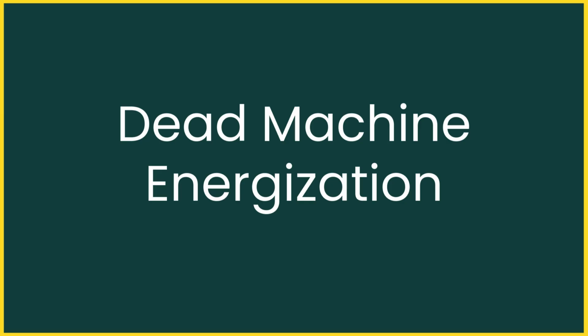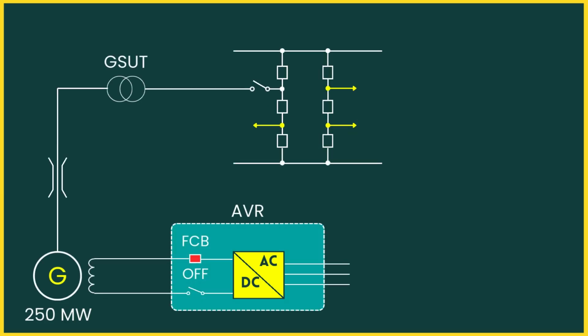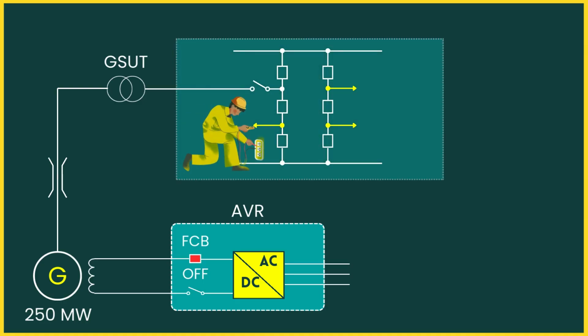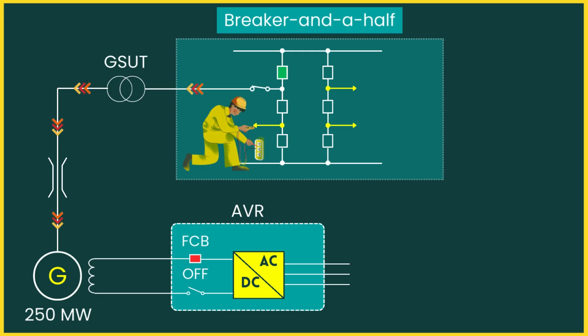To understand how serious this can be, consider one real incident. A 250 megawatt generator in a thermal plant was offline for scheduled maintenance. Its generator protection had been disabled, assuming it was not needed while the machine was offline. A switchyard commissioning engineer, thinking the generator was safely offline, decided to test the control circuit in an adjacent bay of a breaker-and-a-half scheme. During the test, a wiring mistake occurred. And because of that unseen error, the generator bay isolator and breaker closed unintentionally, energizing the machine.